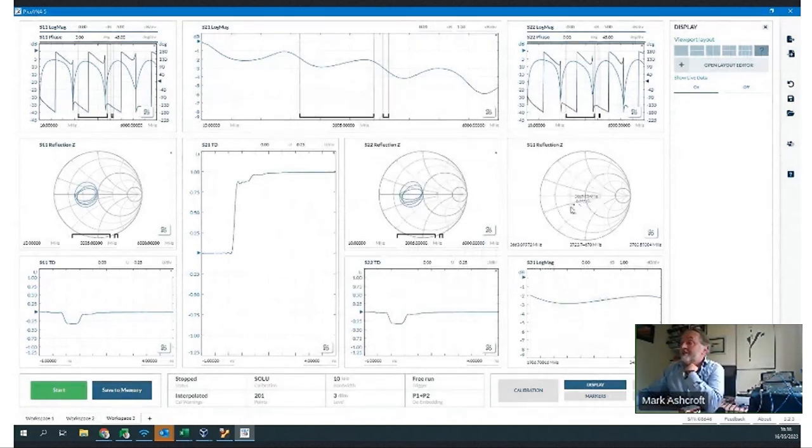I've got, it's a very short one now. Oh, I made that a bit short. A very short Smith here, and I've got another zoom region here, and I can pick as many segments and zoom regions as I wish to. So I could look at multiple channels if I had multiple channel sections in a broadband sweep.